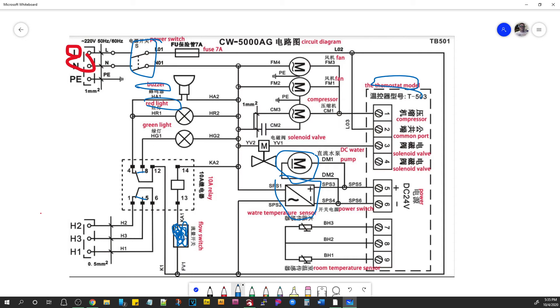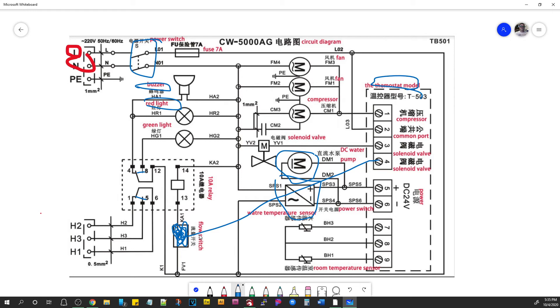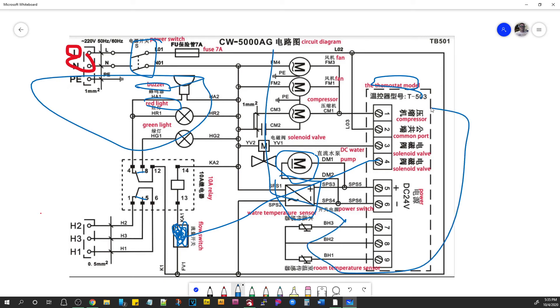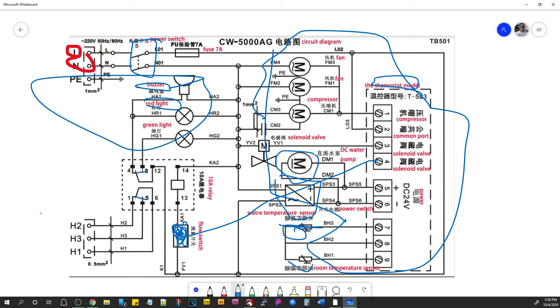That alarm function with the flow switch works totally independently of the controller and everything else. There is no trigger from this flow switch to tell the controller that there's a flow error because it really doesn't matter. If the water's not flowing, you're going to get an error. It's going to stop the laser. But your compressor circuit is still going to continue to function normally. And the reason is it doesn't really matter. If water's not flowing, the temperature's not changing. So it's just going to remain idle until it gets an input from a failure or another sensor that it needs to cycle on or do something else.